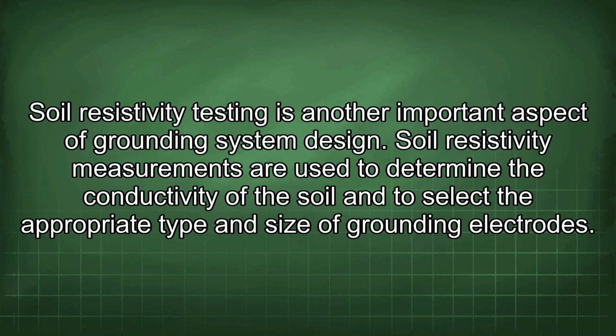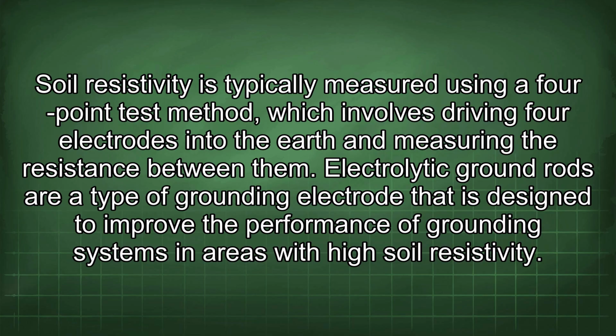Soil resistivity testing is another important aspect of grounding system design. Soil resistivity measurements are used to determine the conductivity of the soil and to select the appropriate type and size of grounding electrodes. Soil resistivity is typically measured using a 4-point test method, which involves driving 4 electrodes into the earth and measuring the resistance between them.